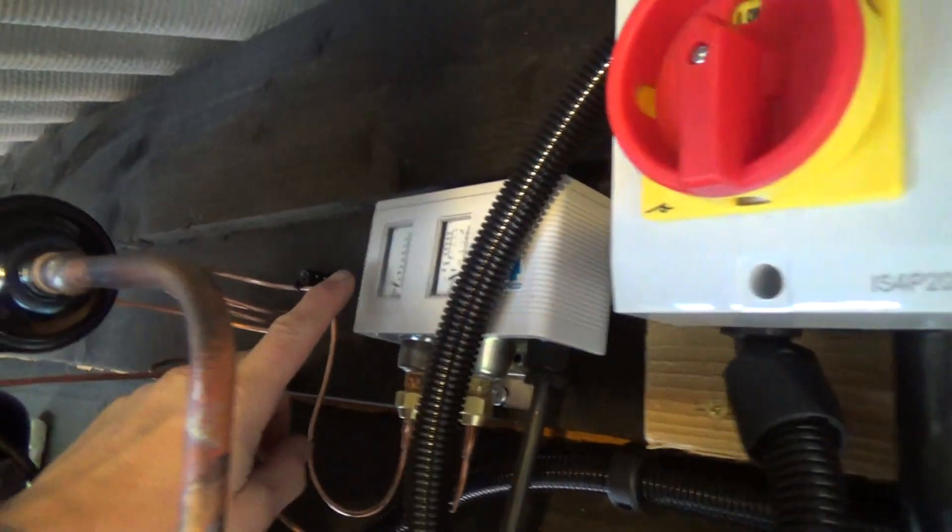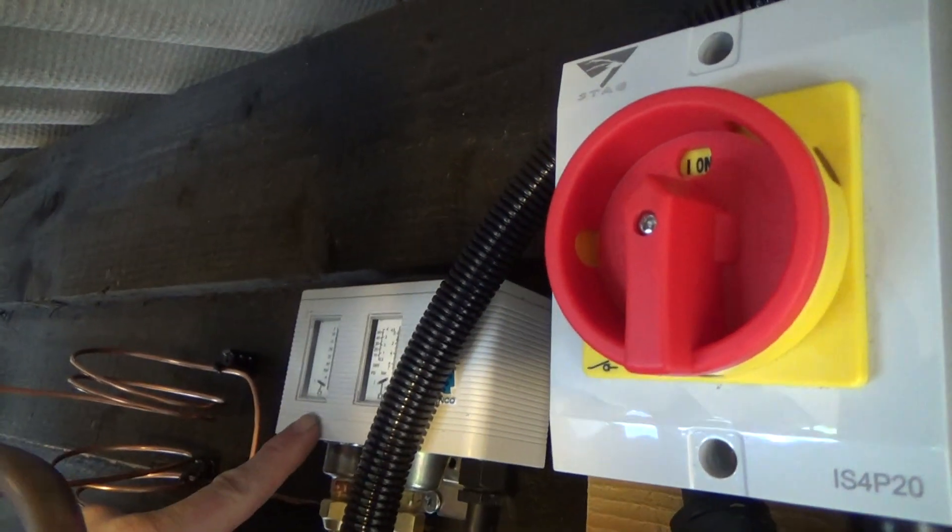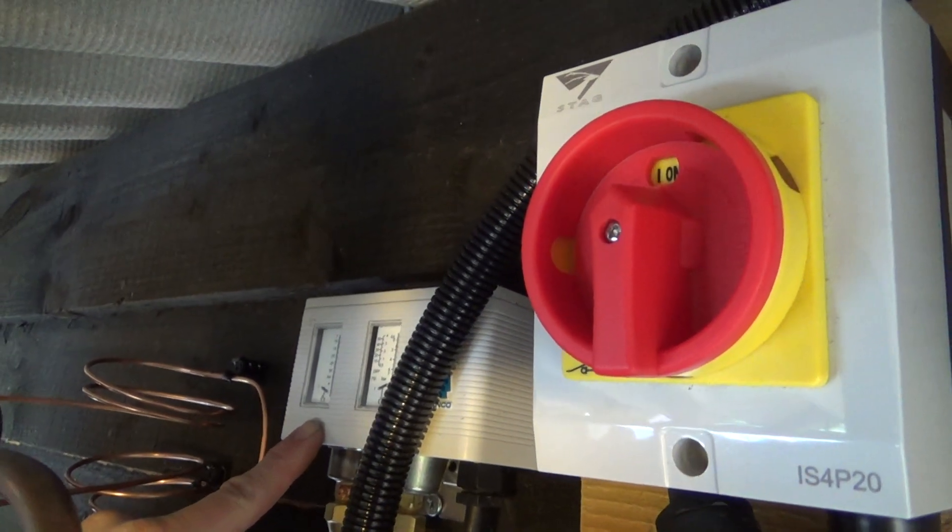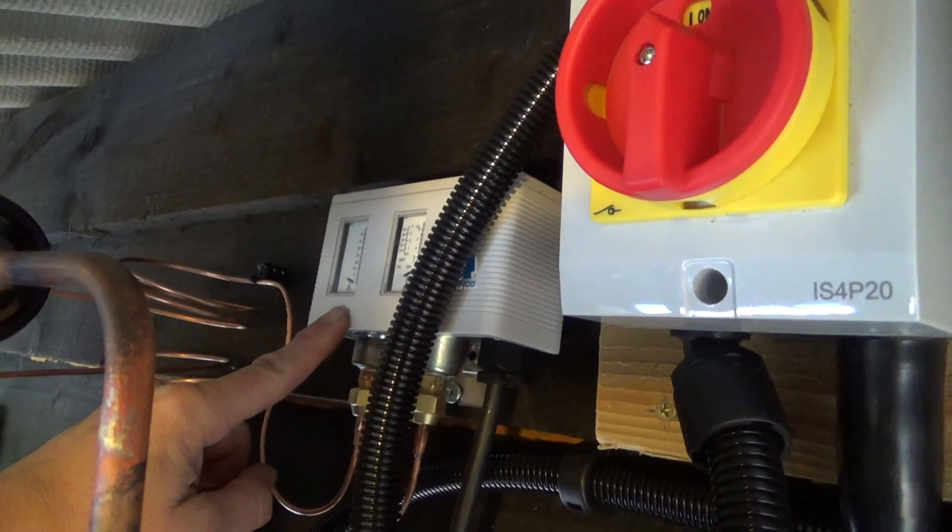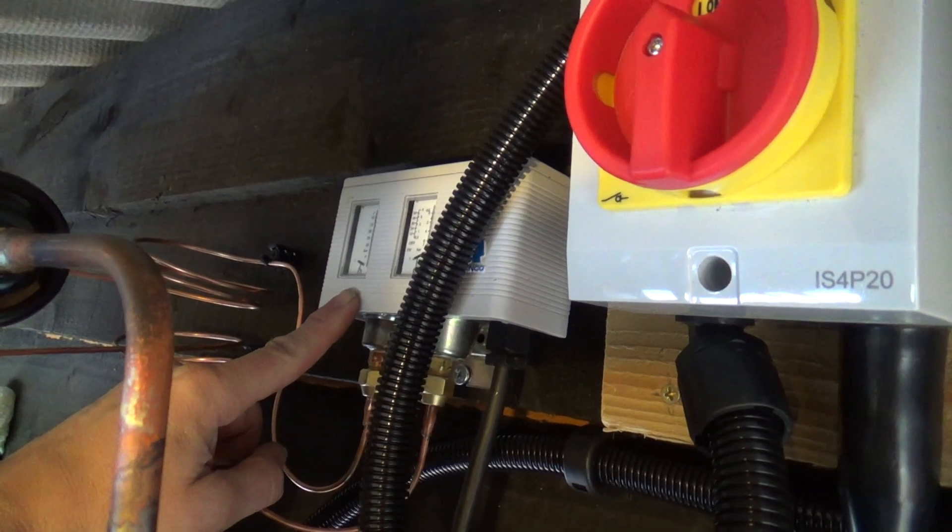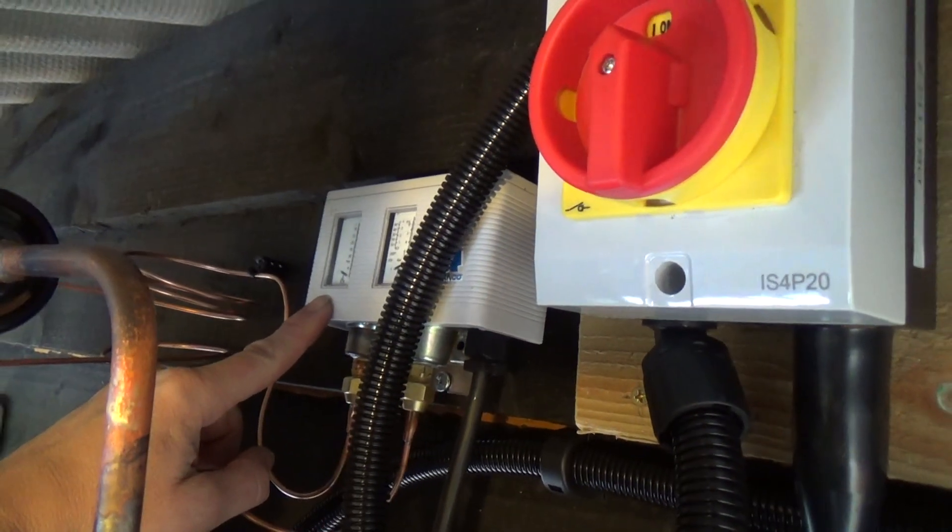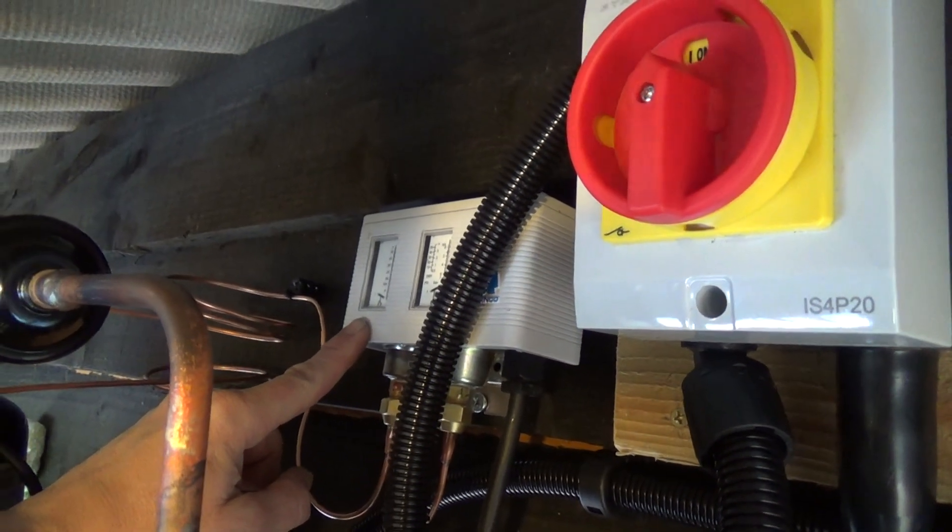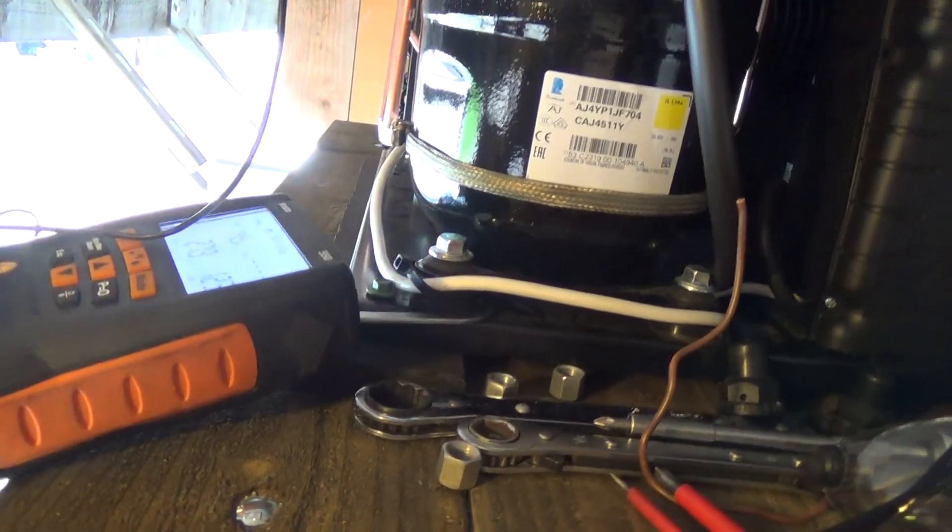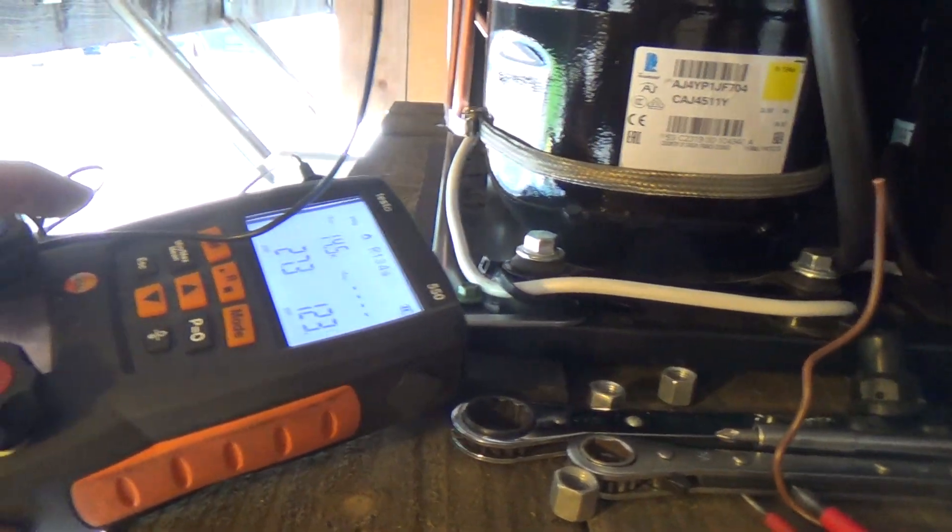Now we've got this set high side to trip about 55 degrees C condensing temp. Hopefully it shouldn't get that hot up here. If you set them too high they can sort of kill themselves with a dirty condenser running at 60 odd for ages before anyone notices.